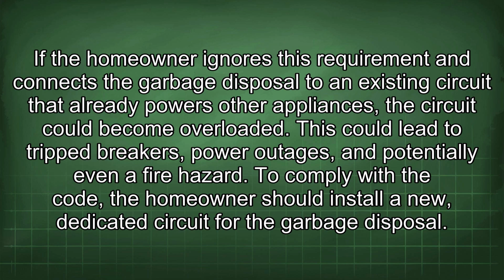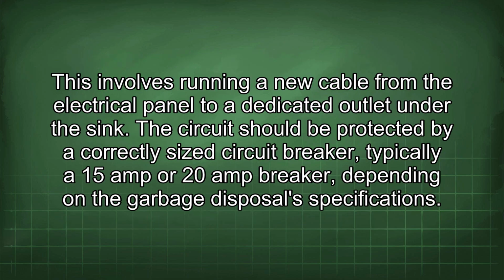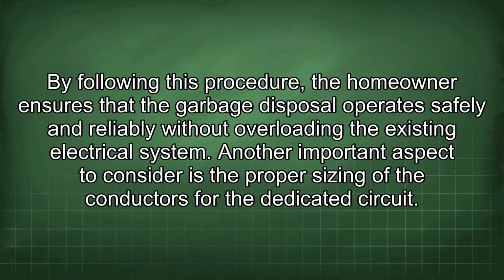To comply with the code, the homeowner should install a new, dedicated circuit for the garbage disposal. This involves running a new cable from the electrical panel to a dedicated outlet under the sink. The circuit should be protected by a correctly sized circuit breaker, typically a 15 amp or 20 amp breaker, depending on the garbage disposal specifications.